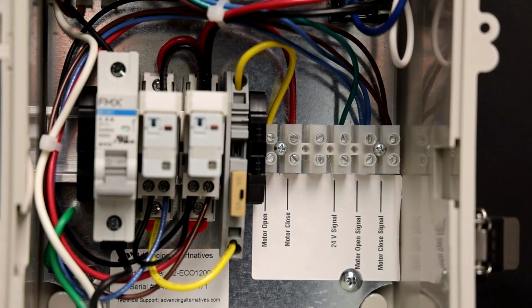For motor connections, we recommend 14 gauge stranded wire for runs up to 200 feet. For over 200 feet, we recommend 12 gauge stranded wire. The motor connections are these two terminals. The two terminals are interchangeable. If the motor runs in the wrong direction, simply swap the wires from one terminal to the other.